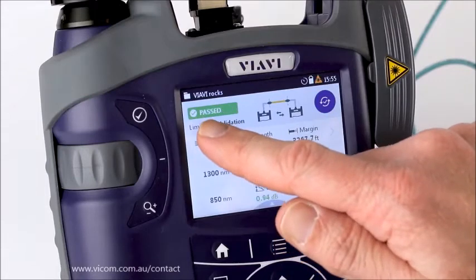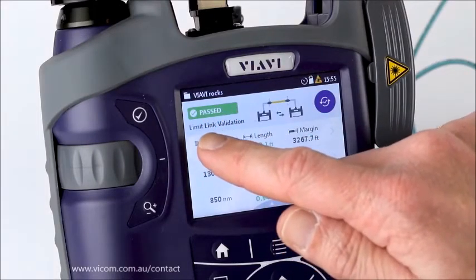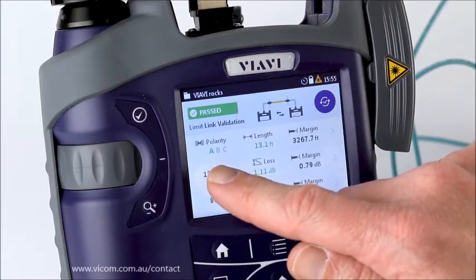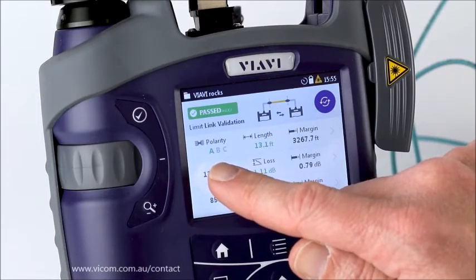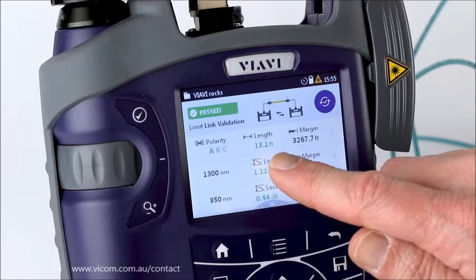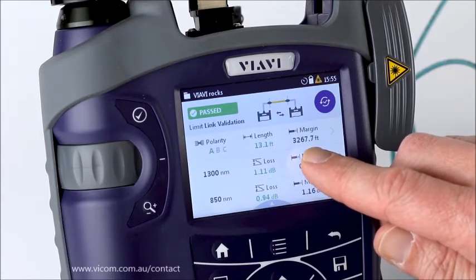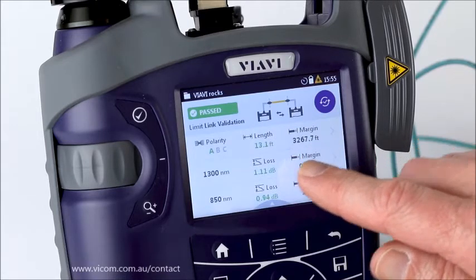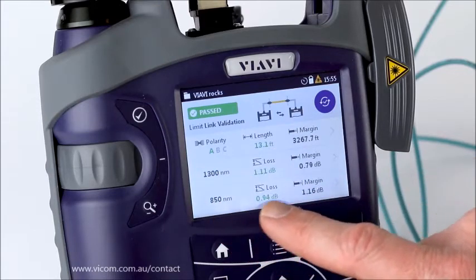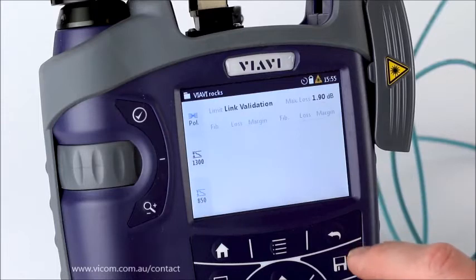I've performed a test and I can see that it passed, though I haven't saved it yet. I can see that my limit was link validation, polarity was set to A — and because A is green it means that was the polarity detected. The length passed at 13 feet, a very short run. Because I had such a long length set for the pass/fail analysis, I can see my two wavelengths, the loss, and the margin.